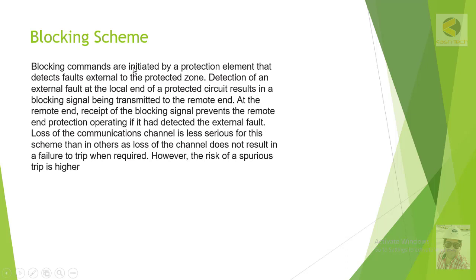A blocking command is initiated by a protection element that detects fault external to the protected zone. Detection of an external fault at the local end of the protected circuit results in a blocking signal being transmitted to the remote end. At the remote end, the received blocking signal prevents the remote end protection from operating if it had detected the external fault. Loss of the communication channel is less serious for this scheme than in others, as loss of the channel does not result in a failure to trip when required. However, the risk of spurious tripping is higher.